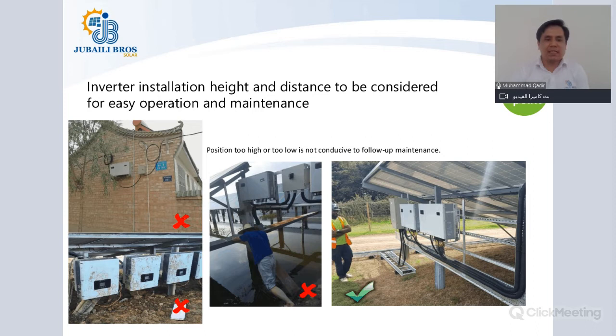Inverter installation height and distance should be considered for easy operation and maintenance. On the screen you can see different pictures. In the one at the top left corner, the inverter is installed at a very big height, and maintenance of such an inverter becomes very difficult. You will need special ladders to climb up there and install, and with two people at that height it becomes very difficult.